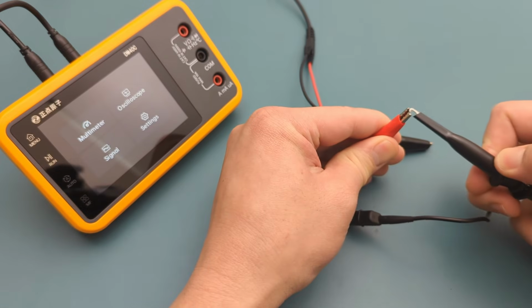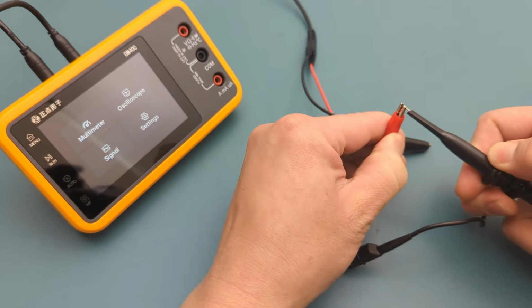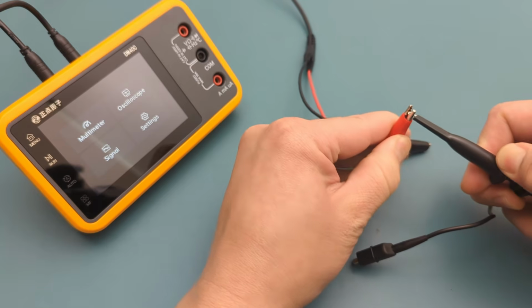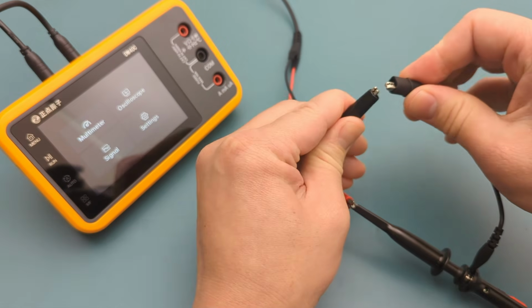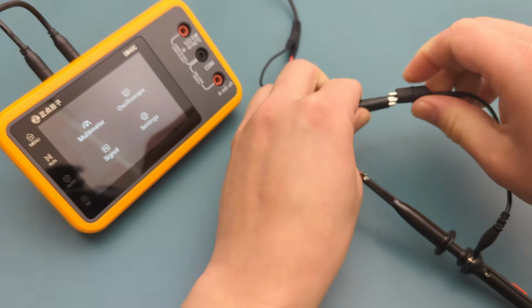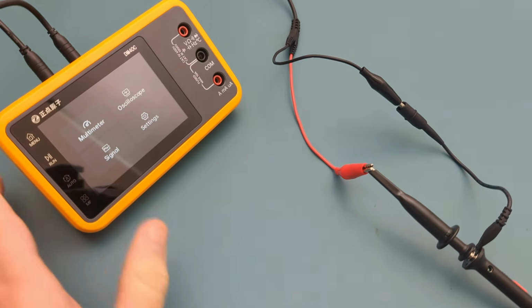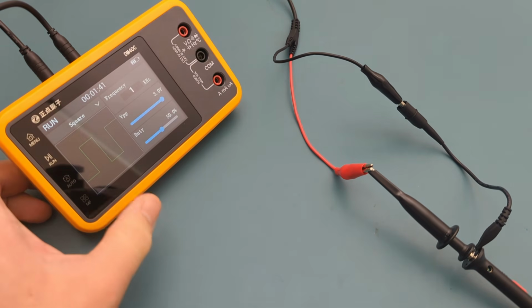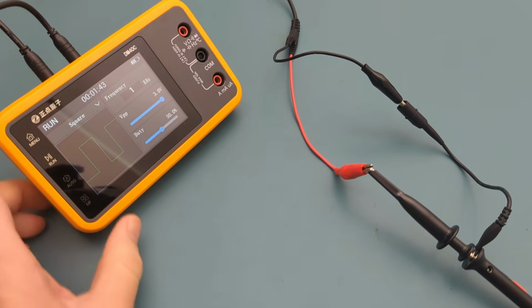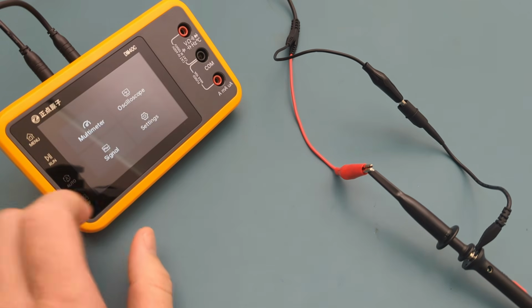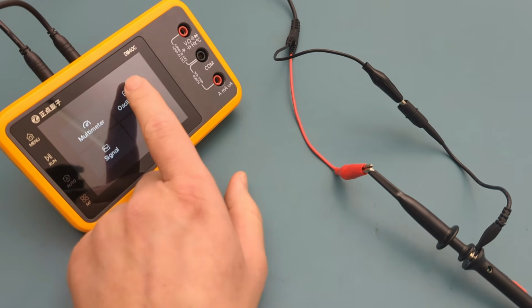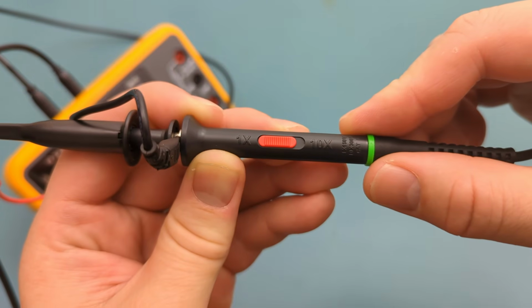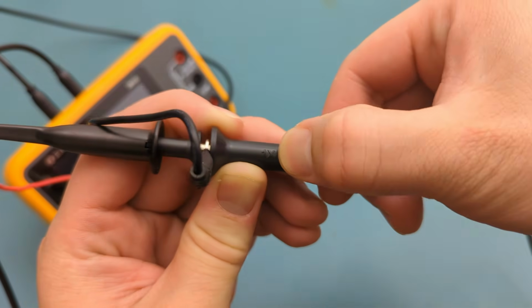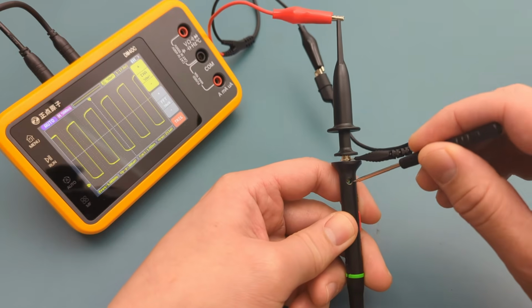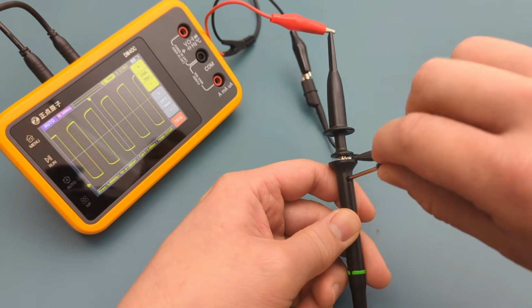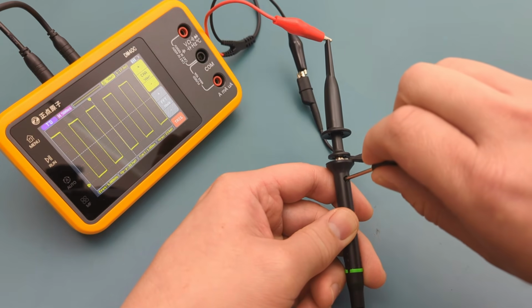Attach the red crocodile clip to the tip of the oscilloscope probe. Attach the ground clip to the black crocodile clip. Press the signal button. All the default settings seem fine. Press the oscilloscope button. Switch the probe from X1 to X10. Use the provided screwdriver to make adjustments until the displayed square wave has sharp, flat edges.